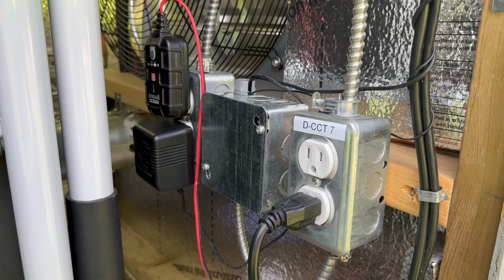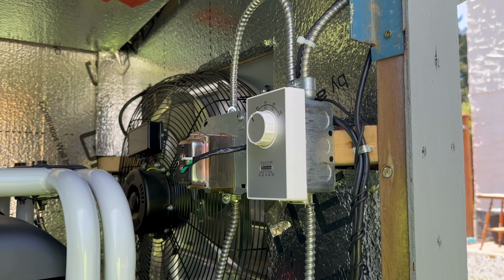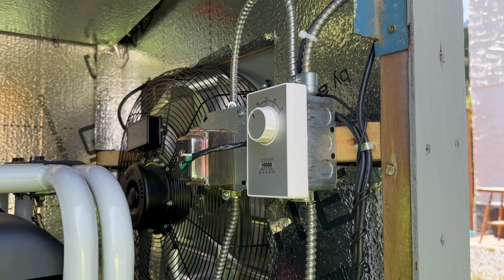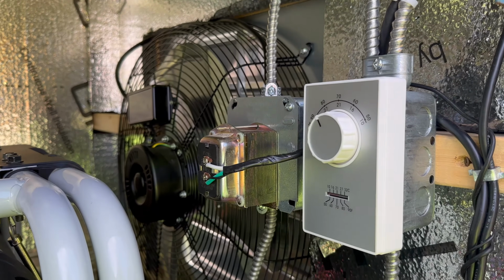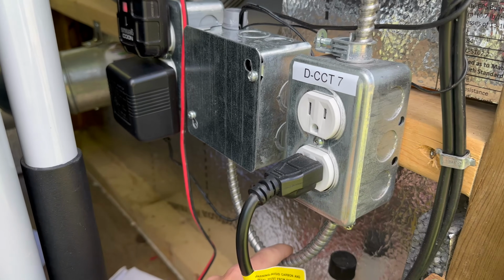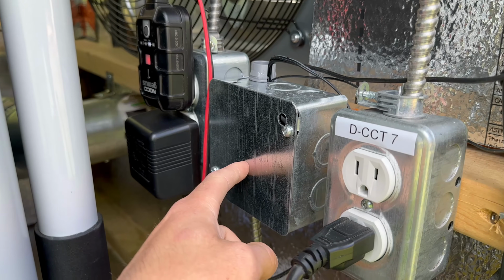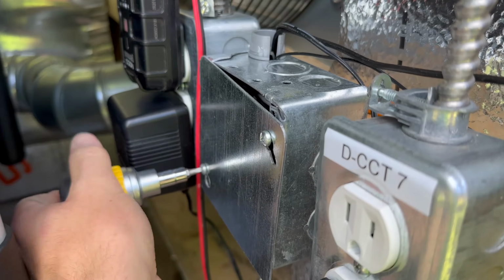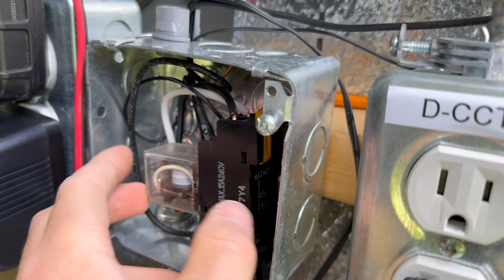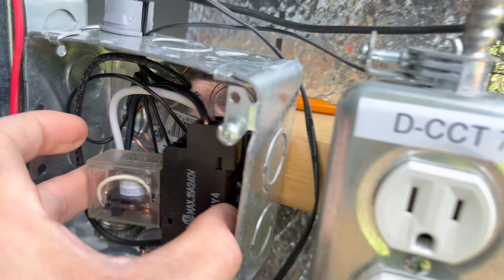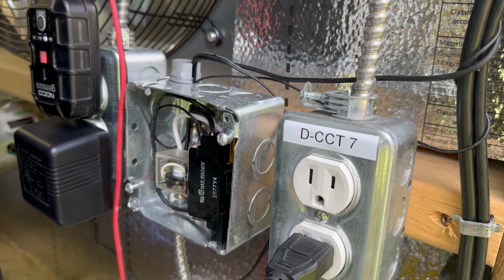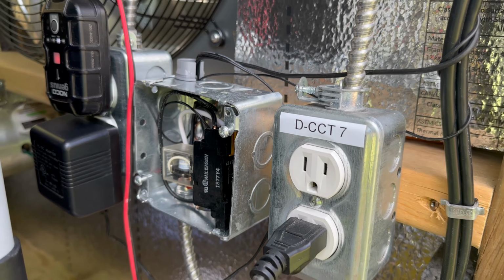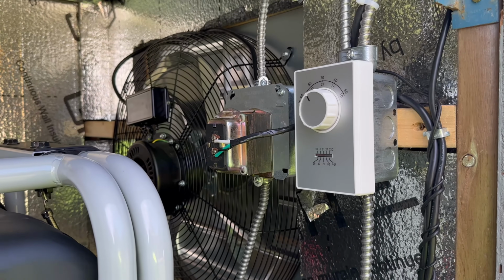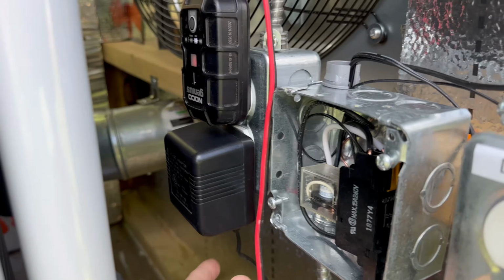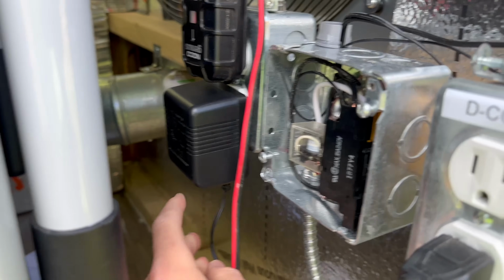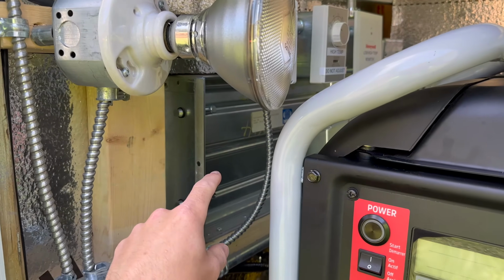However, how it gets that voltage is that it will only get the 10 volts to open when the thermostat decides it's hot enough in here, and that thermostat will then give not only 120 volts to the fan, but it is tied through this receptacle that the fan plugs into this box, which houses a relay. This is a 120 volt coil relay where the 120 volt ties into the top, and it is configured as normally open. So when it has no power, the relay is in the open position, and when it receives 120 volts at the same time as the fan does from the thermostat, the relay will close, allowing this transformer right here that puts out 10 volts to travel through the relay and go to the damper to open.